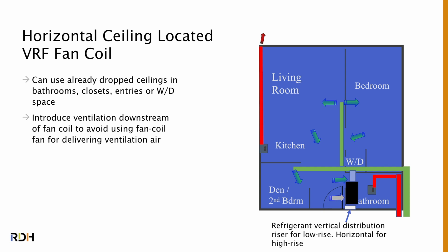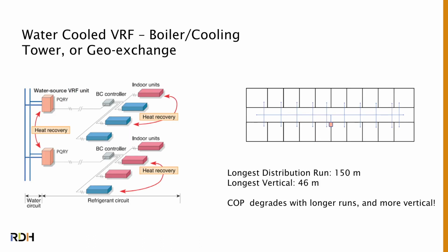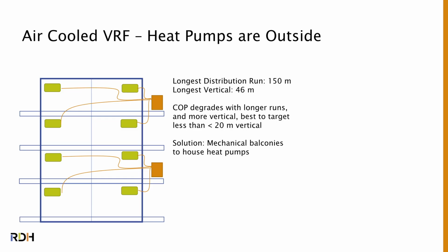With the water-cooled ones, you can install the water-cooled heat pumps, one on every floor or two or three on every floor, depending on the size of the load. Again, you need a vertical distribution riser. With the air-cooled heat pumps, you pretty much can only go about 40 meters vertically. As your building gets taller, you start losing COP, so I would recommend trying to keep it around 20 meters vertical.